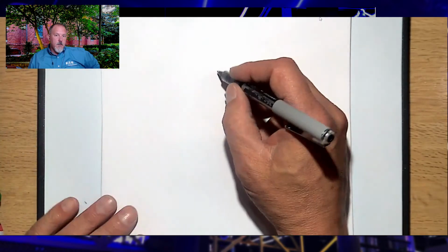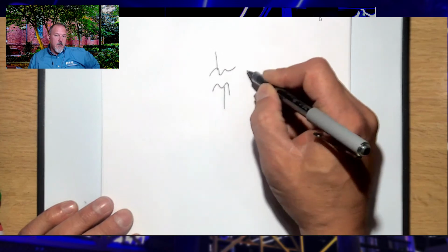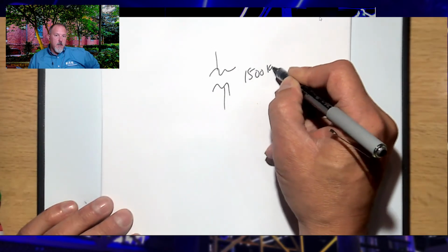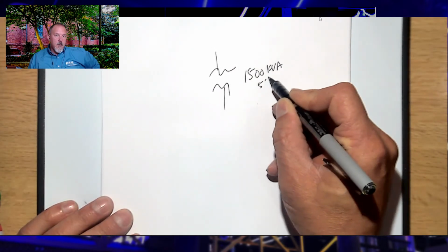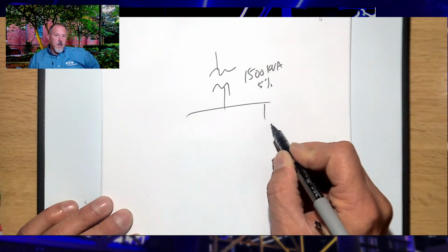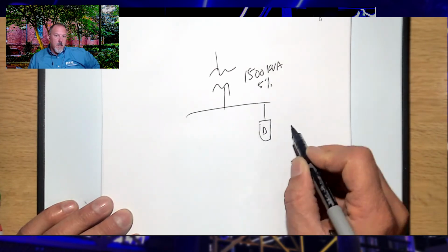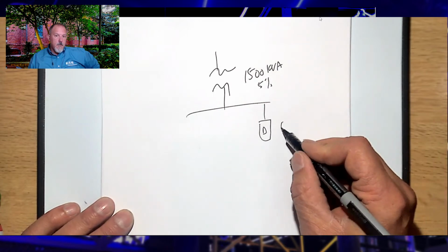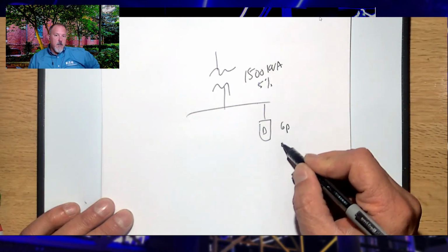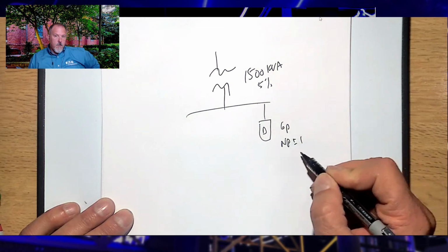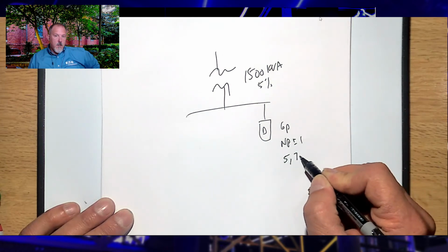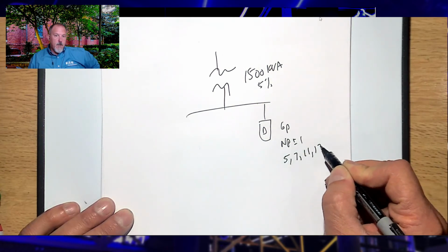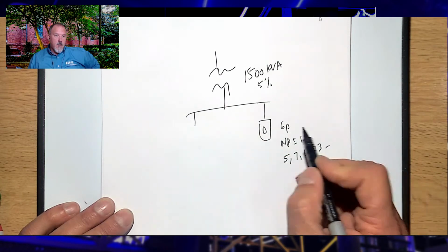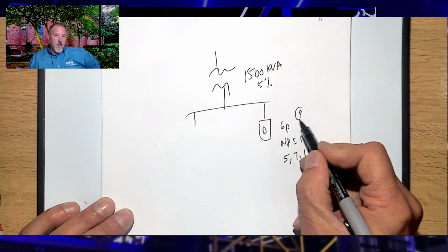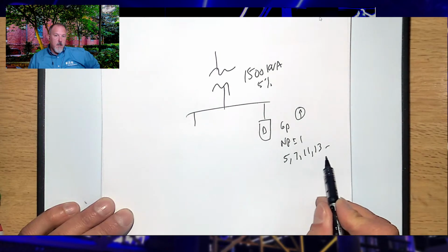Now, the easy calculation for that is, say you have a 1,500 kVA transformer, 5% impedance. Then you have a load here that's a drive, and you know which harmonics it's going to produce. If it's 6 pulse, it's NP plus or minus 1: 5, 7, 11, 13, etc. That's my harmonic source, so I know I'm going to produce fifth harmonic, 7th, 11th, 13th.